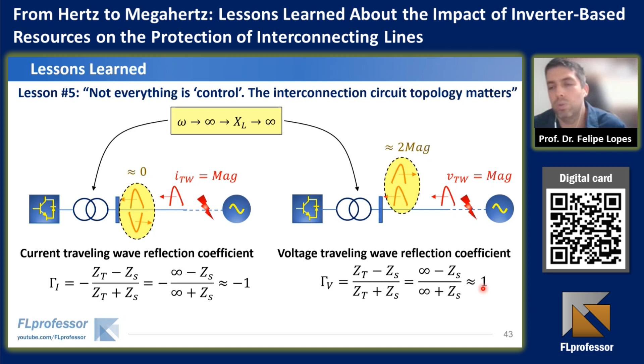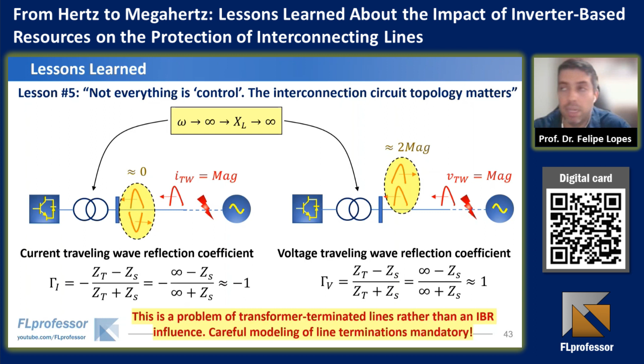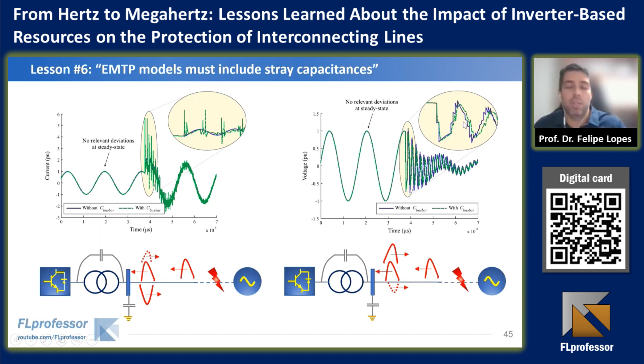And we started to investigate such a question, especially from the aspect of testing relays using simulated data. So a careful modeling is recommended, especially of line terminations. And this is why we had the lesson 6, where we say that EMTP models must include stray capacitances, because depending on the stray capacitances at the busbar and across the transformer, voltages and currents may completely change their behavior from a transient perspective. In these figures, without the busbar stray capacitance we have almost nothing in terms of transients in the currents, but when the busbar capacitance is included, the transients take place. And the opposite behavior is verified regarding voltage transients. So this is an important aspect.